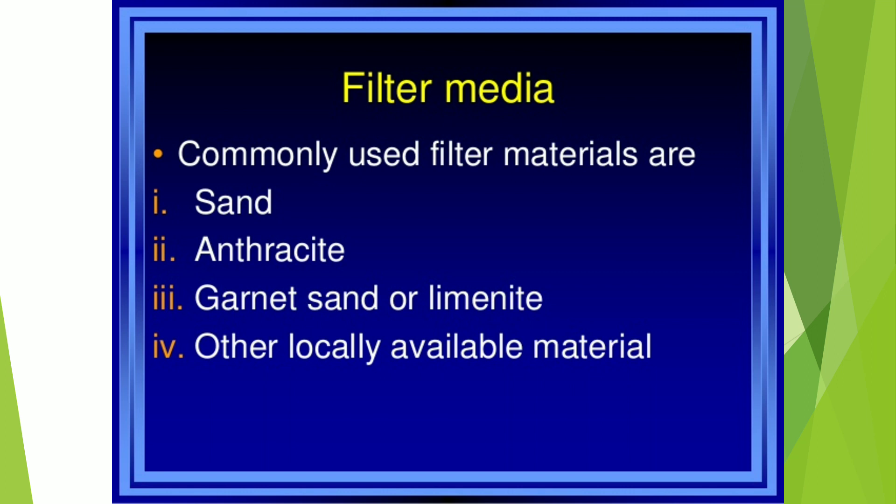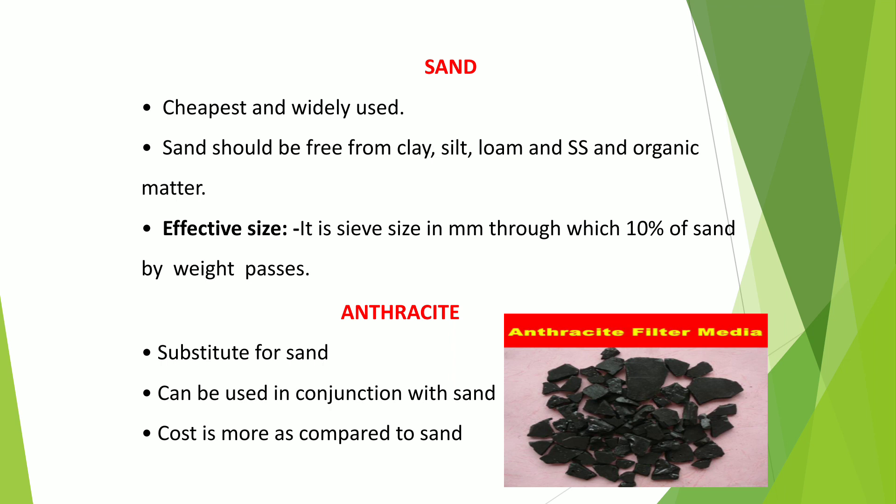The main consideration in filtration is the filter media and which type to use. Commonly used filter mediums are sand, anthracite, garnet sand, and other locally available materials. Sand is generally used as filter media — it is the cheapest and most widely used. Sand should be free from clay, silt, loam, and organic matter, as these fill the pores and prevent filtration. The effective size is around 10% of the sand by weight. Anthracite filter media is a substitute for sand, can be used in conjunction with sand, but costs more. Garnet sand is heavier than normal sand, with a specific gravity of 4.2, and is used in mixed media filters.